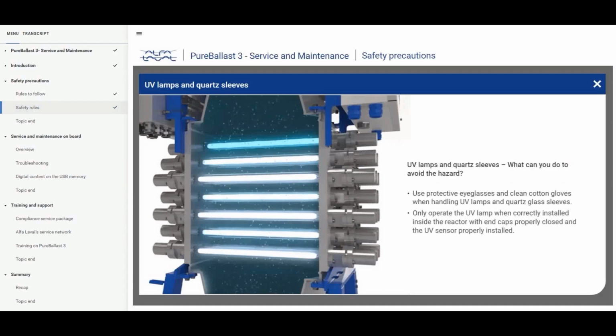Always use protective eyeglasses and clean cotton gloves when handling UV lamps and quartz glass sleeves. Only operate the UV lamp when correctly installed inside the reactor, with end caps properly closed and the UV sensor properly installed.